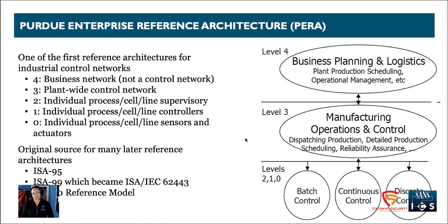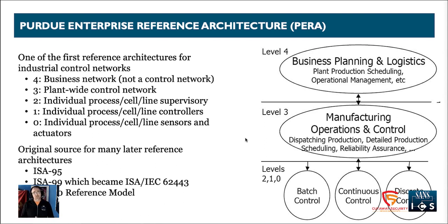Levels zero, one, and two are organized into lines or cells, also referred to as processes. This terminology differs from sector to sector. We're going to have multiple processes in an organization, and those tie into a larger portion of the network — mainly to communicate with master servers on the plant-wide control network. Master servers at level three include things like Active Directory, asset management, and data historians.